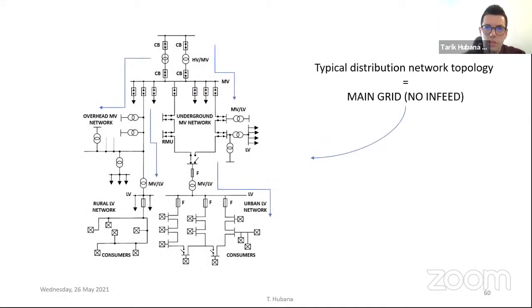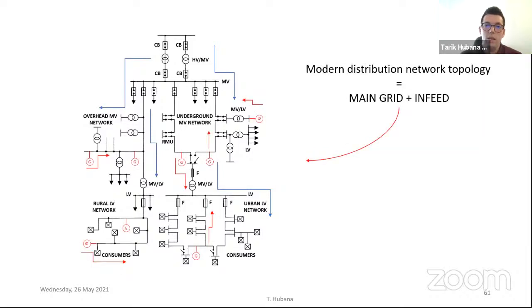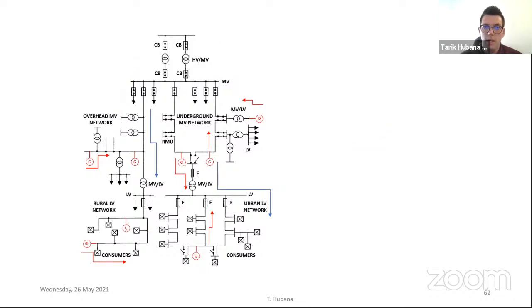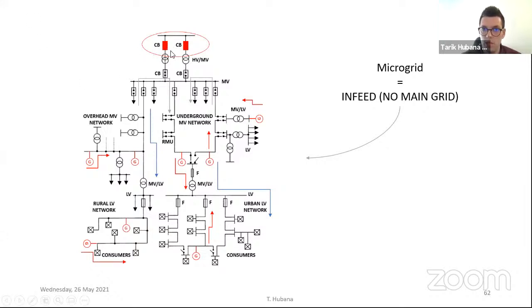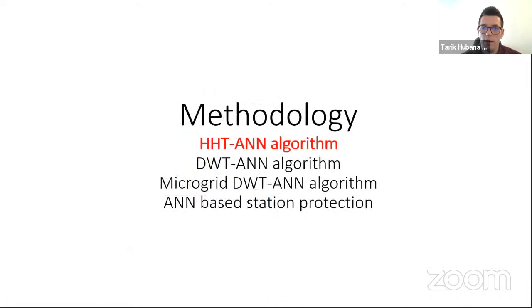Here we see a traditional distribution network. Again, now we are speaking precisely in terms of medium voltage distribution networks. This is a typical topology. This typical network throughout history did not have distributed generation, so we only had the in-feed from the grid. In modern times, of course, renewables showed up. Now we have these DGs in our system, and the load flows within the system are changing. And finally, with the disconnection of the grid at the point of common coupling, which is here on these circuit breakers, these kinds of networks can go into islanded mode of operation and work as a microgrid.